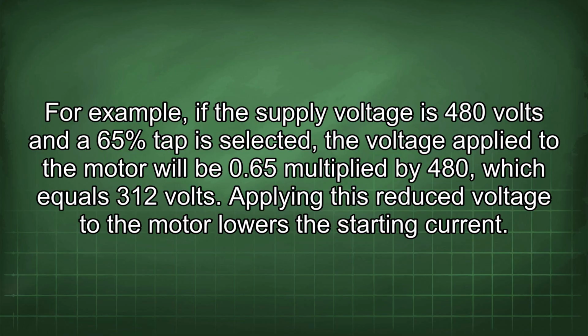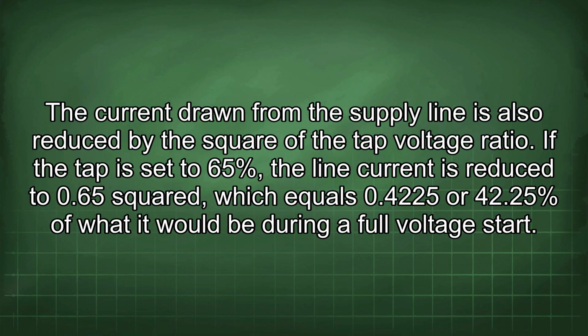Applying this reduced voltage to the motor lowers the starting current. The current drawn from the supply line is also reduced by the square of the tap voltage ratio. If the tap is set to 65%, the line current is reduced to 0.65 squared, which equals 0.4225 or 42.25% of what it would be during a full voltage start.